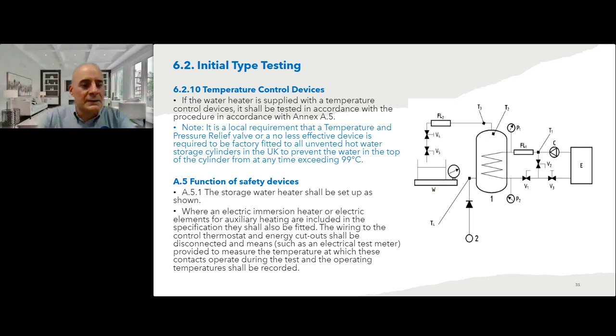So A5 then is the function of safety device. The storage water heater should be set up as shown, where an electric immersion heater or heating are included in the specification. They should also be fitted. The wiring to the control thermostat and energy cutouts should be disconnected, and means such as an electrical test meter or LED indication lamps provided to measure the temperature at which these contacts operate during the test, and the operating temperatures should be recorded.